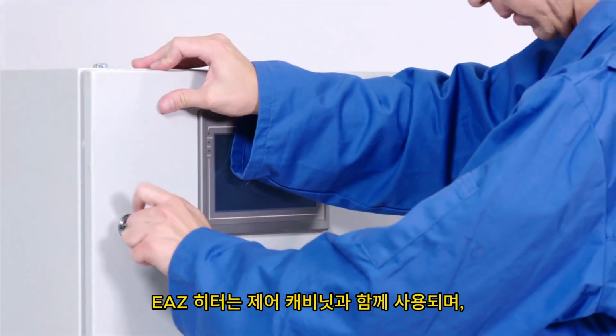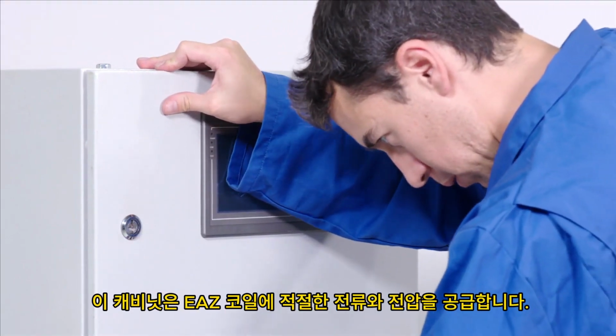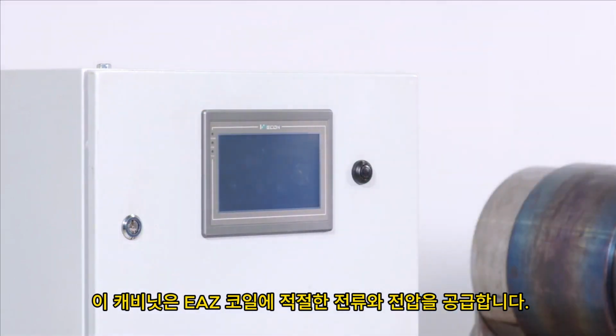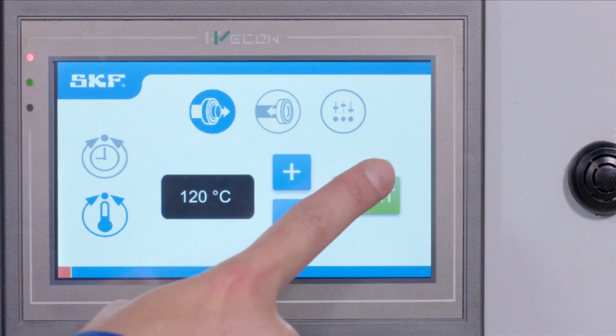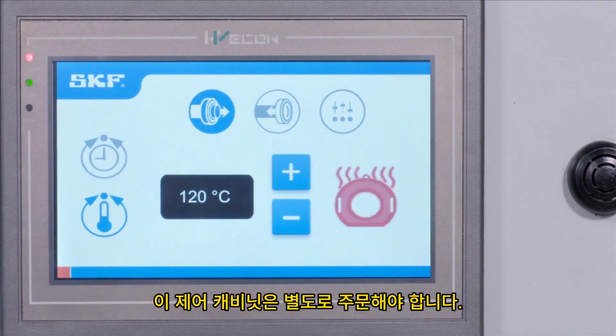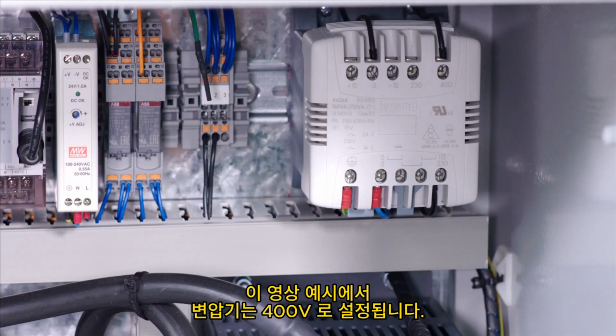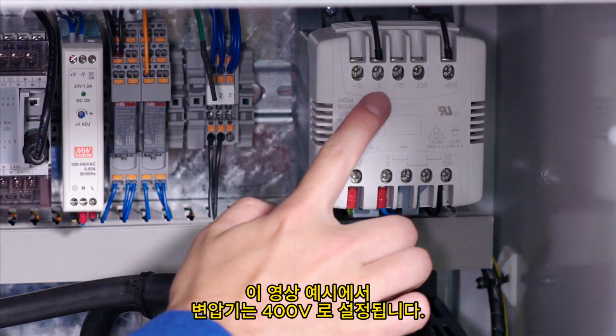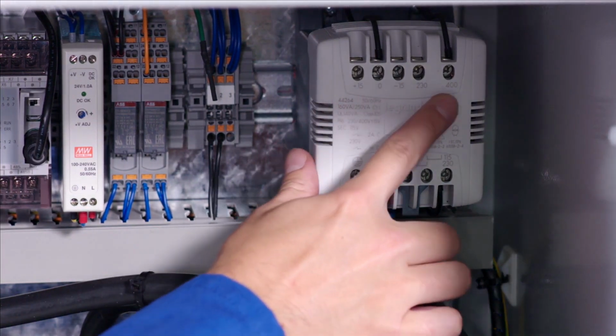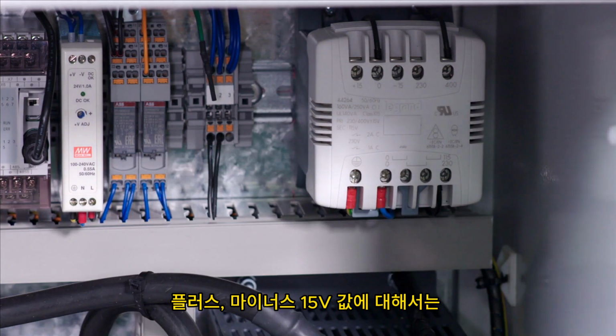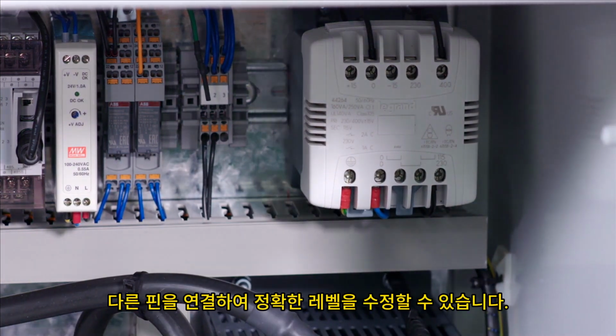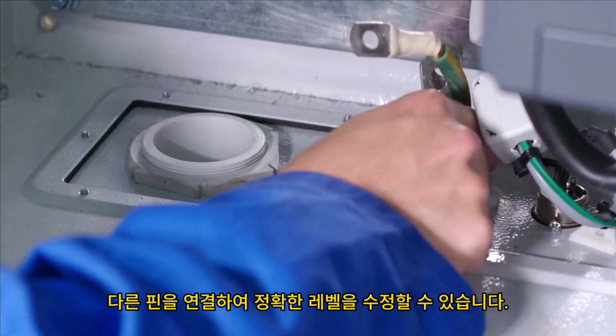EAZ heaters are used with a control cabinet which supplies the right current and voltage to the EAZ coil. This control cabinet must be ordered separately. In this example, the transformer is set to 400 volt input. You can correct the exact level by connecting the other pins for plus or minus 15 volts.